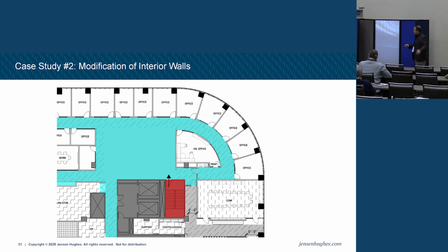Let's say it's a over 75-foot tall high-rise building that has stairwell pressurization in it. I decide I want to take this out, and this is going to be an open office area now. We'll put cubicles there. And we're doing this all over the place on a regular basis. Okay, so the original design, this section here is part of my means of egress. So I have to pressurize that with my stairwell pressurization system.